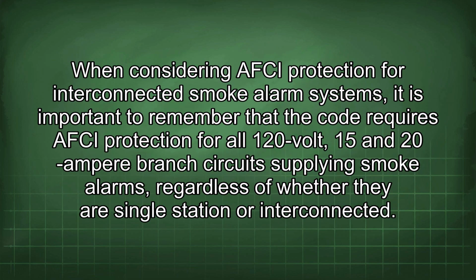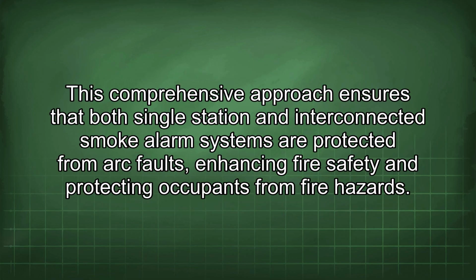When considering AFCI protection for interconnected smoke alarm systems, it is important to remember that the code requires AFCI protection for all 120-volt, 15 and 20 ampere branch circuits supplying smoke alarms, regardless of whether they are single station or interconnected. This comprehensive approach ensures that both single-station and interconnected smoke alarm systems are protected from arc faults, enhancing fire safety and protecting occupants from fire hazards.